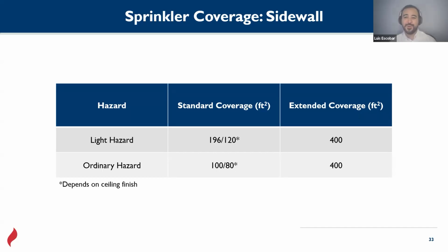Sometimes, as I was saying, we are always asking, please send me the updated structural plan, because we need to confirm the depth of the beams and the space between them, so we can space our sprinkler heads. Sometimes if the beams are too deep, we need to go lower in this number, and that's a critical case. So the system works when there's a fire, in case there's a fire. Hopefully not, but if there is a fire, we need to make sure the system is going to work. Extended coverage sprinklers cover more area, but they demand more water because they need to protect more area, and we cannot have an area where there won't be water released.